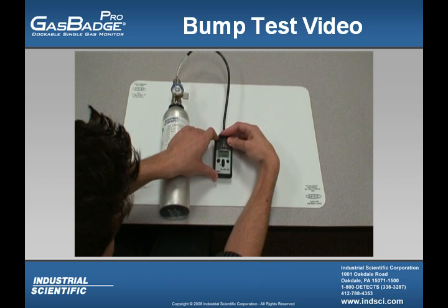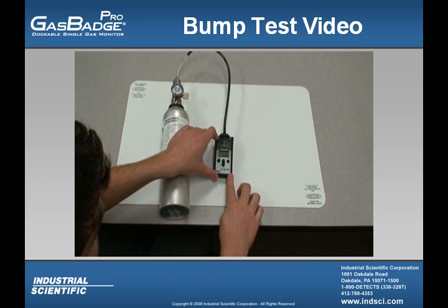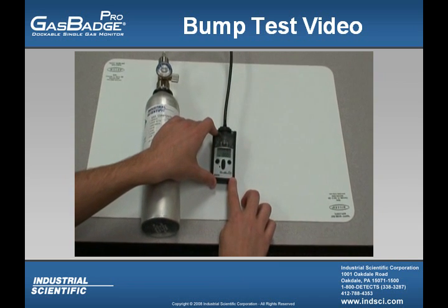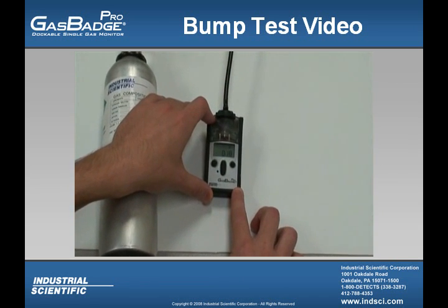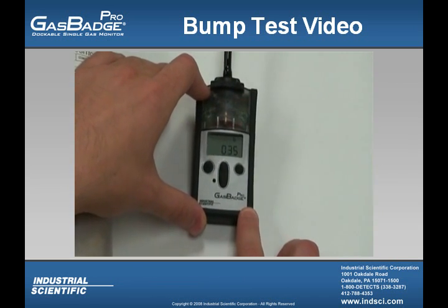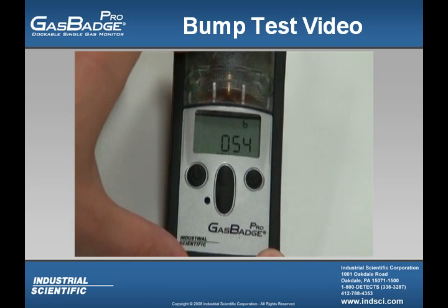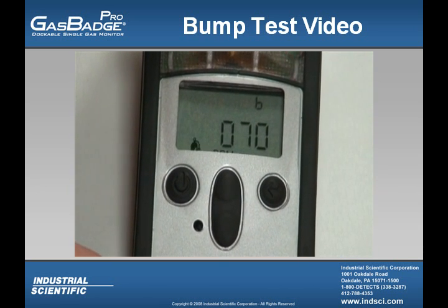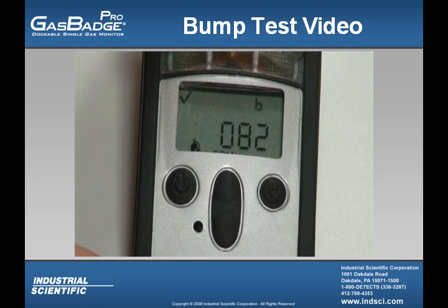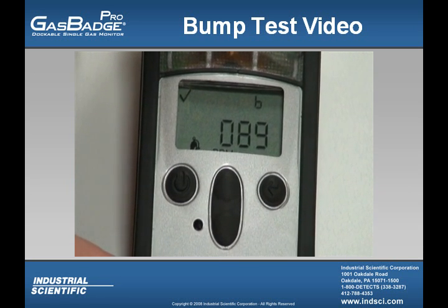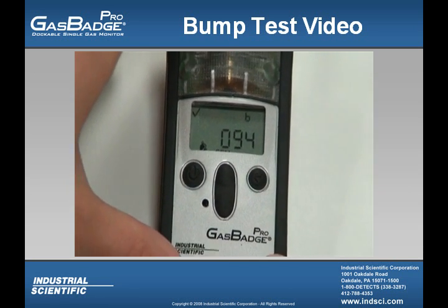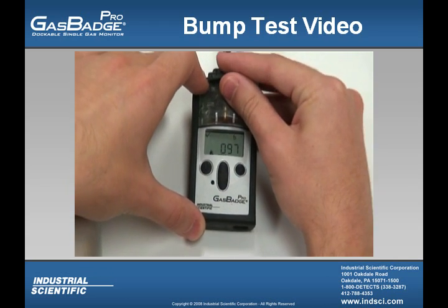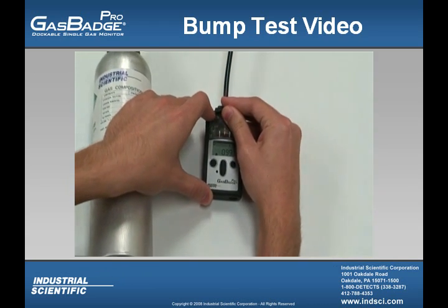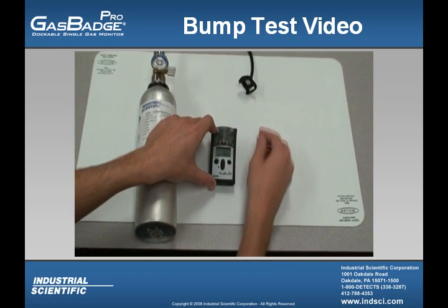From there, you're going to see the screen on the GasBadge Pro increasing. You're going to wait for the GasBadge Pro to finish the bump test. From there, you'll see a check mark in the upper left-hand corner, and you'll see the instrument emit a short beep. From there, you're just going to want to wait for the GasBadge Pro to go back into the real-time operation screen, and the bump test is finished.